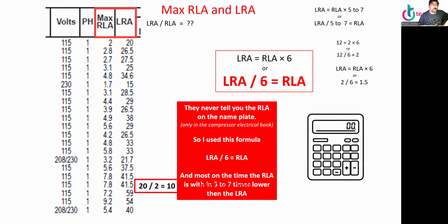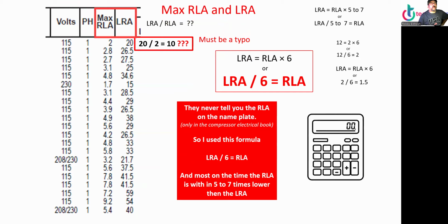So it says maximum. So the first one must be a typo. There's no way, 2 and 20. I mean, come on, compressor 10? I don't think so. So only 1, 2, 3, 4, 5 are not within the range, are not between 5 to 7 times. The rest are within 5 to 7 times. How you like that? Isn't that cool?